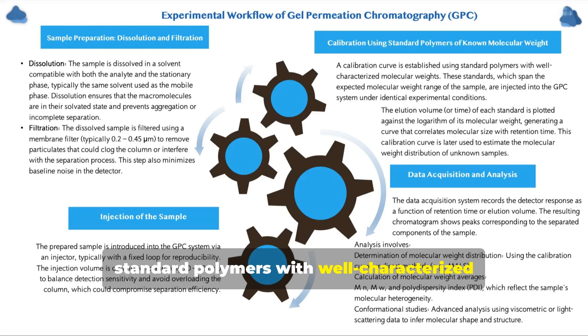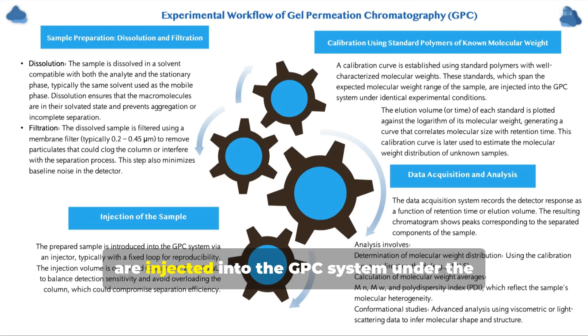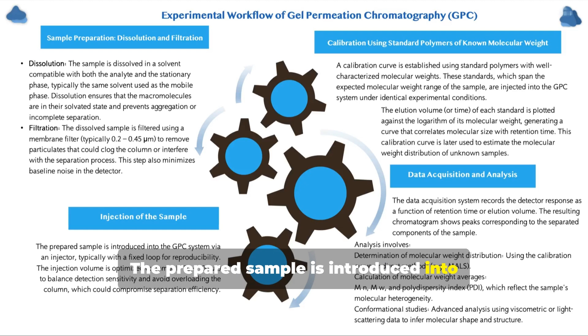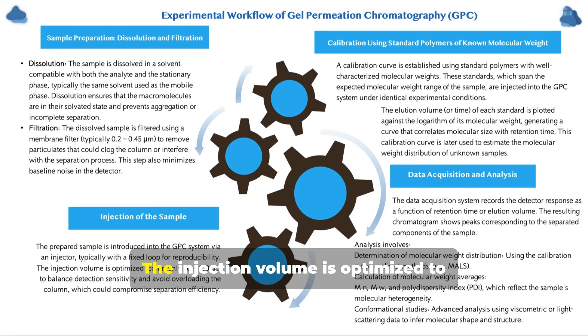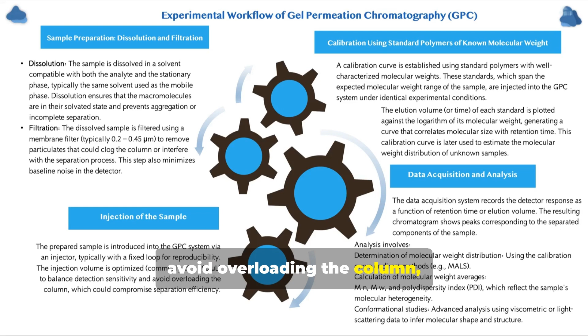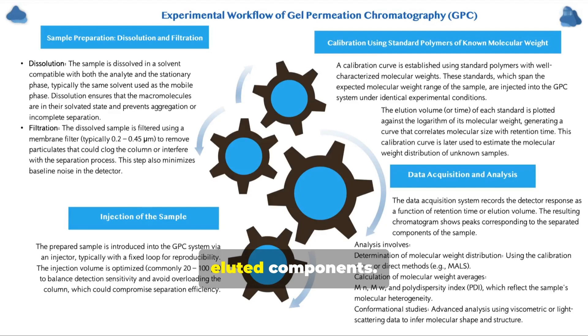Next, a calibration curve is established using standard polymers with well-characterized molecular weights. These standards cover the expected molecular weight range of the sample and are injected into the GPC system under the same experimental conditions. The prepared sample is introduced into the GPC system via a feeder, typically using a fixed loop to ensure reproducibility. The injection volume is optimized to balance detection sensitivity and avoid overloading the column, which may compromise separation efficiency. During the run, the detector continuously monitors the eluted components.